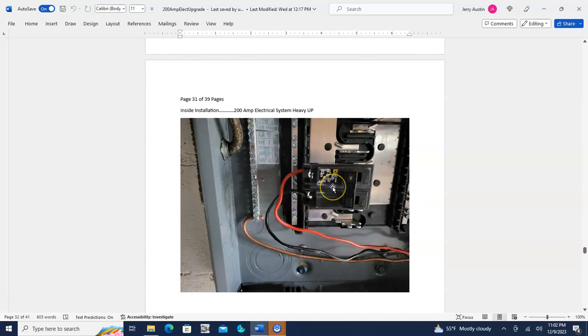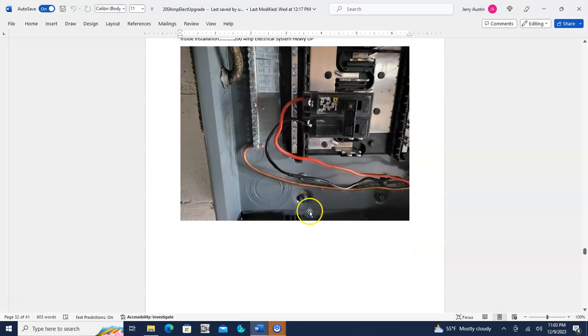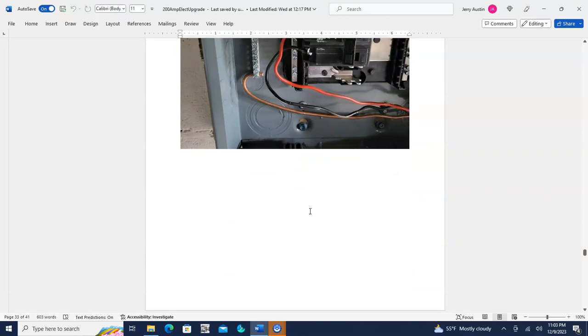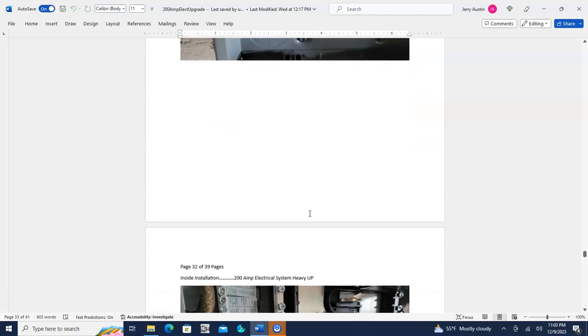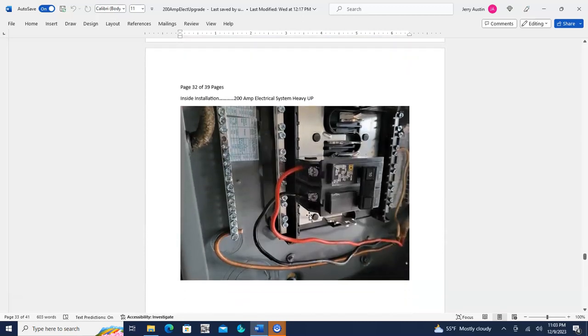This is a 220 circuit breaker right here, and they're using red and black, and that is either for a dryer or for something that uses 220. Once again, that's another picture of the same thing there. You can see this real good picture here of this safety ground here, and the wire that goes over and hooks into the other safety ground. This bus right here is the electrical ground bus, and over here is the other electrical ground bus. And the circuit breakers hook right onto these leads right here.